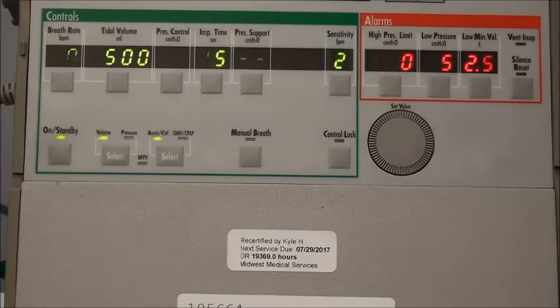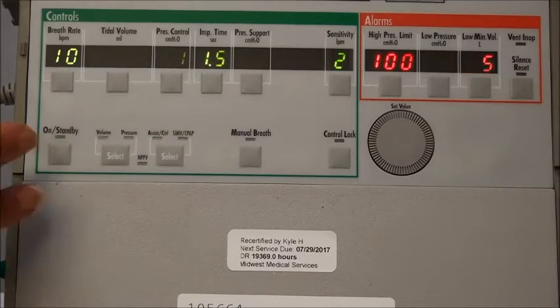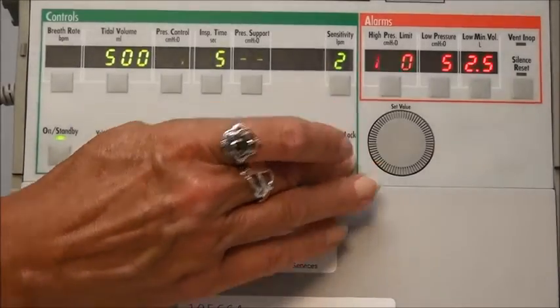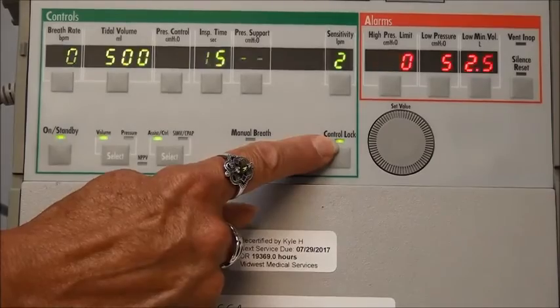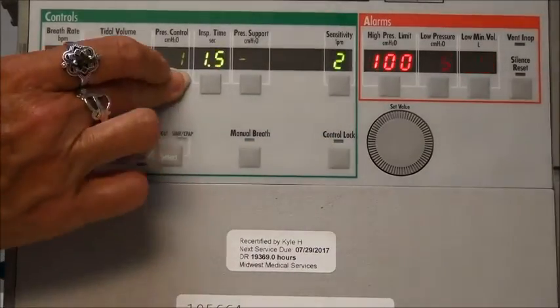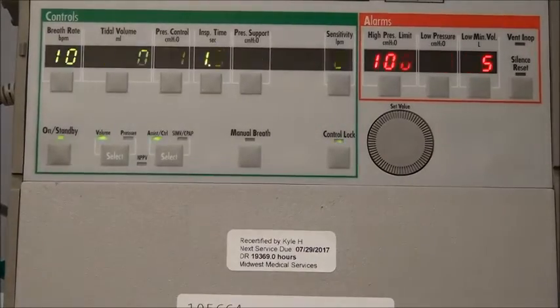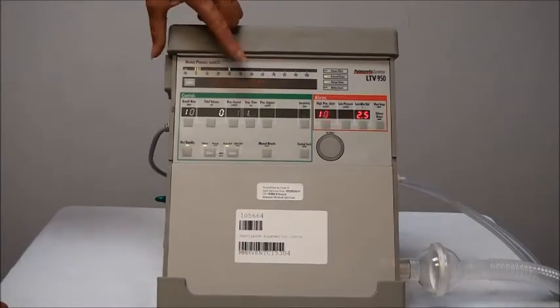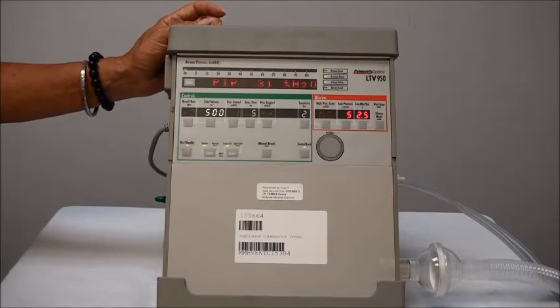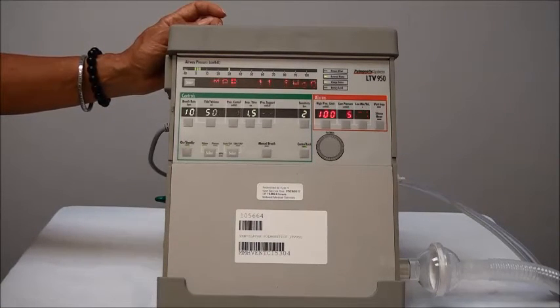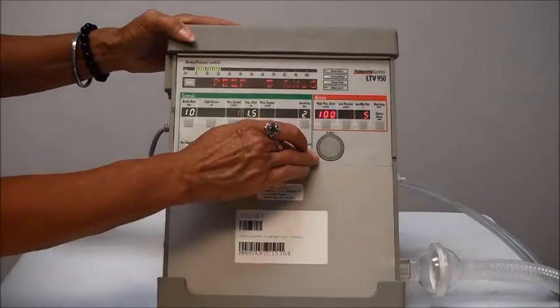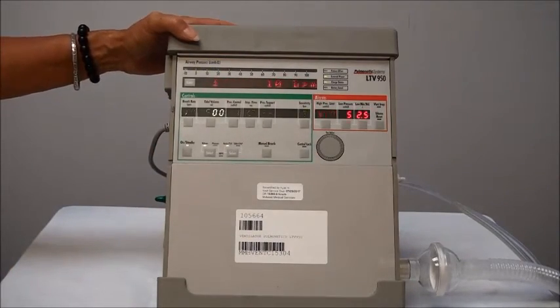Again, this is just in case something gets set wrong or somebody accidentally comes in and pushes a button and sets it where it's not supposed to be. That's just a way of you getting back and knowing how to change it back to where it needs to go. Now down in this corner there's a control lock. If I push that button, you see how the green light comes on under control lock? I can't change any settings when it's locked. And if I try to do that, it's going to tell me it's locked. I'm also not going to be able to shut the ventilator off if it's locked. So if I want to change any settings or turn the ventilator off, I'm going to need to come over and push that control lock to make the green light go out.